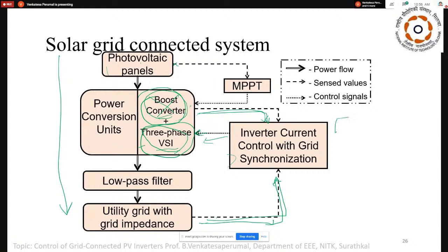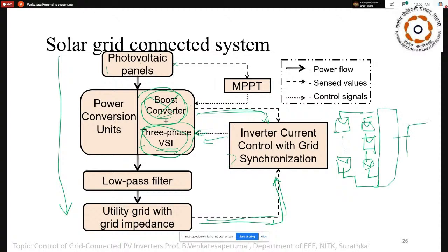So what the boost stage exactly does is, many array combinations use a boost converter configuration. If you see, this is my one array point, and this is array number 1, and array number 2 will be combined in the combiner box. Then it goes to the MPPT box, and then it goes to the DC to DC converter. The next stage is the DC to AC. So here a number of arrays are combined and used for the DC to DC converter, but in a central inverter there is no DC to DC converter.